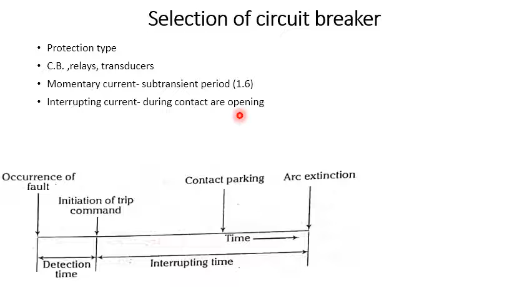Then the interrupting current is the current present during contact opening. It is lower than the momentary current, and is the current flowing through the breaker when its contacts open. This current depends upon the speed of the circuit breaker, between the occurrence of the fault and the extinction of the arc. It is normally specified in cycles of the power frequency. For one cycle at 50 hertz, 1 by 50 is 0.02 seconds. The standard speeds of circuit breakers are 8, 5, 3, 2 or 1.5 cycles. It is recommended to use the subtransient reactance model for synchronous generators and the transient reactance model for synchronous motors.